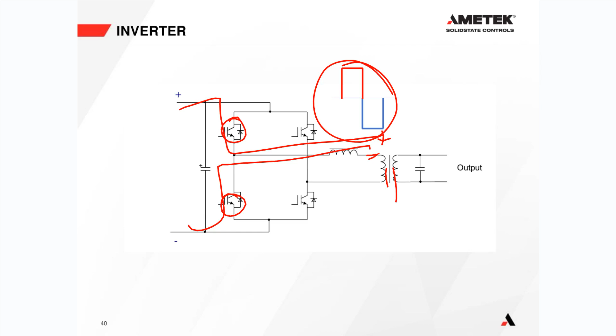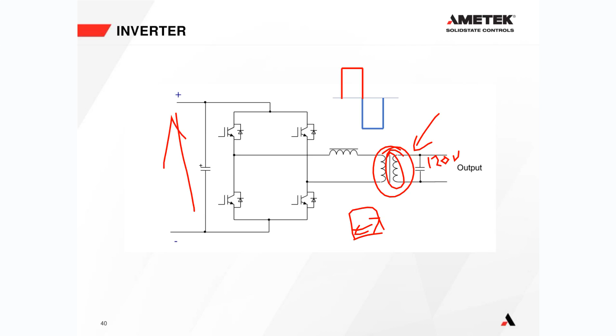Rather than a normal transformer, regulation isn't done by changing pulse width. Instead, the transformer is a constant voltage transformer, or ferroresonant transformer, and that transformer does the regulation. We have a tank circuit that saturates the transformer at a certain point, so the output stays at 120 volts independent of the input. It's a slightly different, more robust design, but the output regulation isn't quite as good as with the PWM circuit.